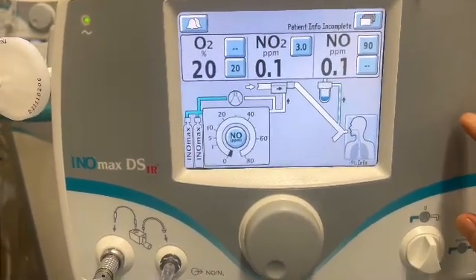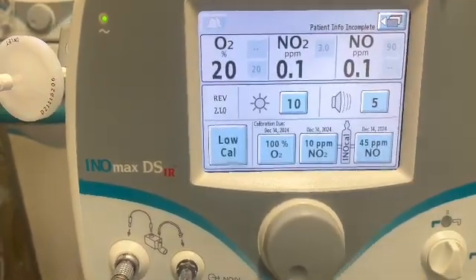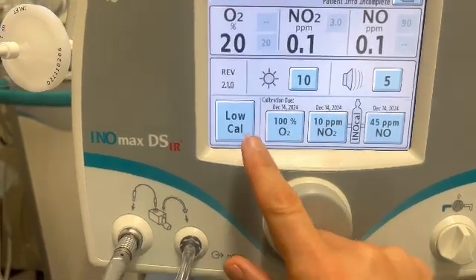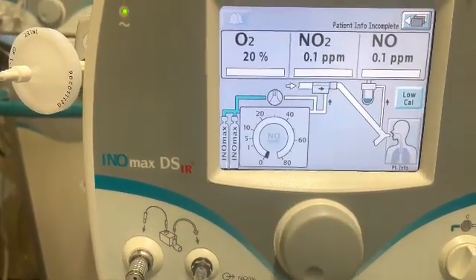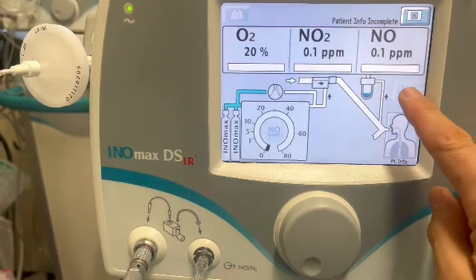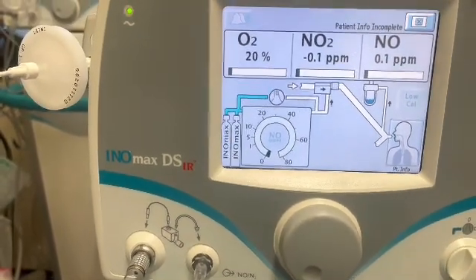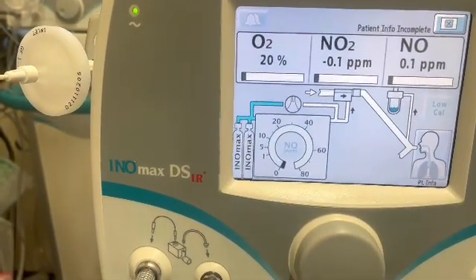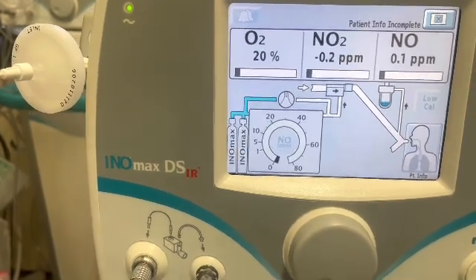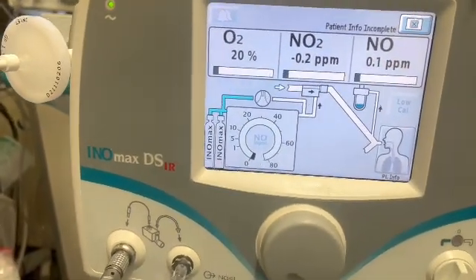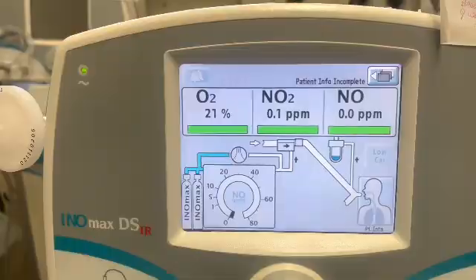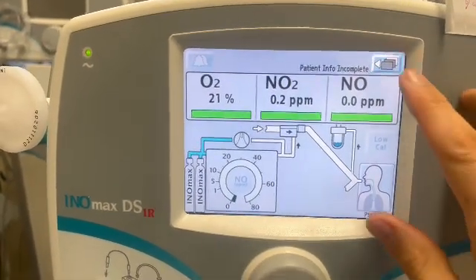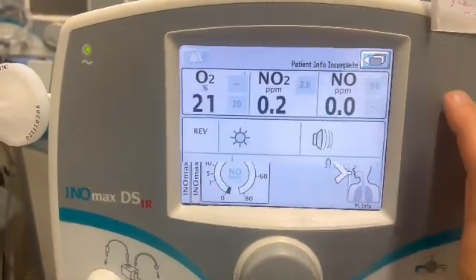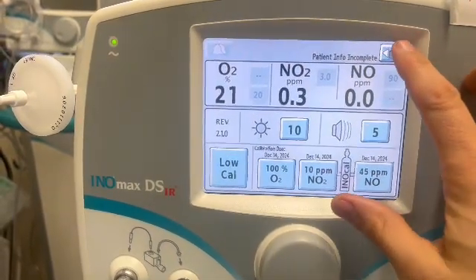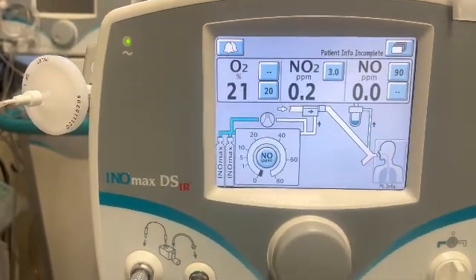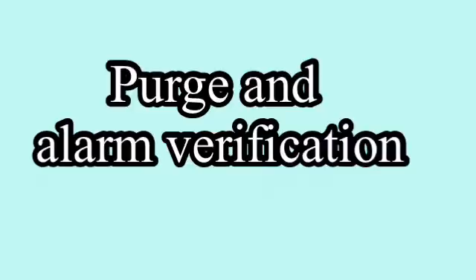To perform a low calibration of the machine's sensors, go to the top right hand icon and press low calibration, and press low calibration again. The machine now performs a low calibration of the sensors to atmospheric air. Green bars show a successful calibration. Red bars would show the calibration had failed. Press the top right hand icon twice to get back to the main menu.